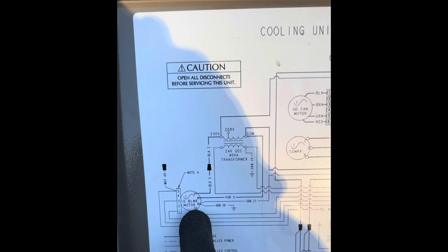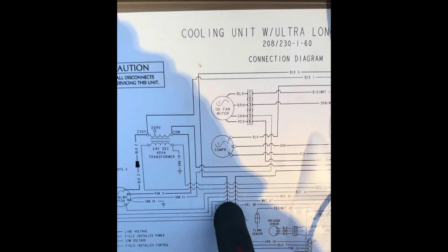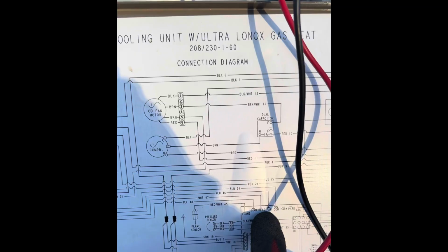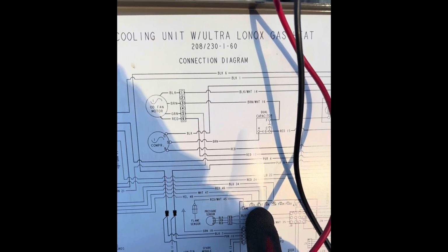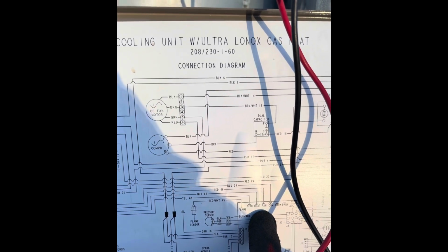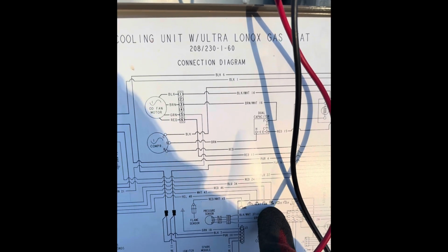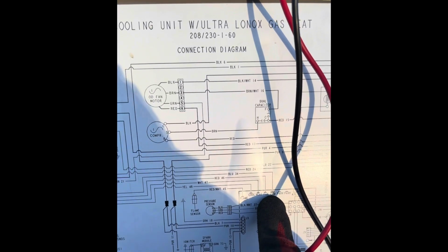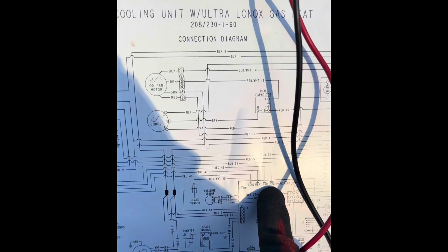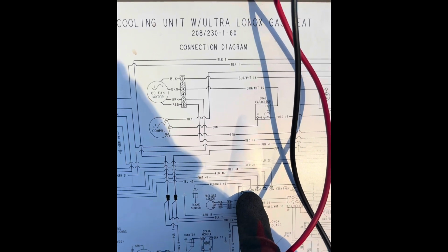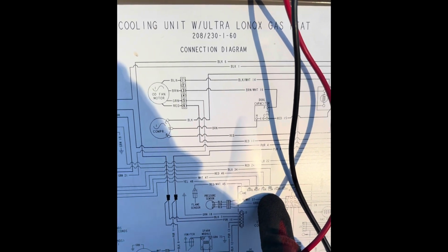If you took a look at the diagram here, you're going to see the indoor blower motor, you have your common, then you have your signals coming from your control board here: cool, heat, fan, and common. So when you call for these signals, let's say for fan only, you should have 24 volts between common and fan. For cooling, you'll have common and cool, and for heating, you'll have heat and common.